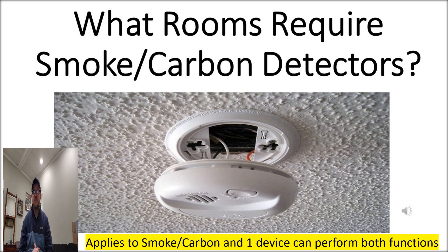This is not an all-inclusive list, but here are examples of when you may need carbon monoxide detection as well. If you have an attached garage — whether it's below, to the side, or above the structure — if you have a wood-burning stove even if you don't use it, if you have a stove insert even if you don't use it, or if there is gas to the structure at all — even if it's capped off and you don't use it — you're likely going to have to have carbon monoxide detection.